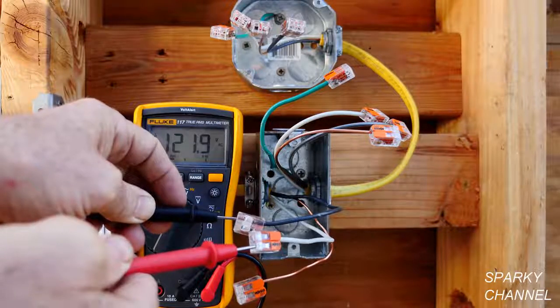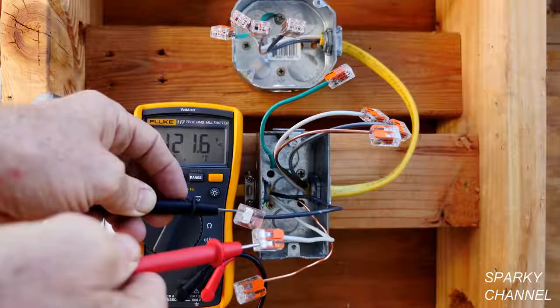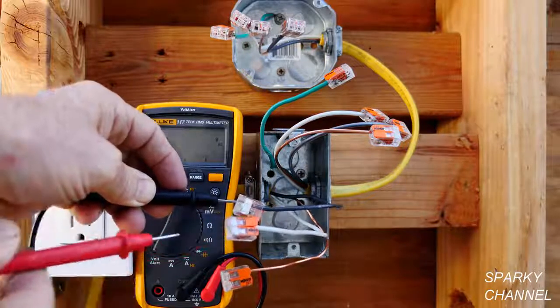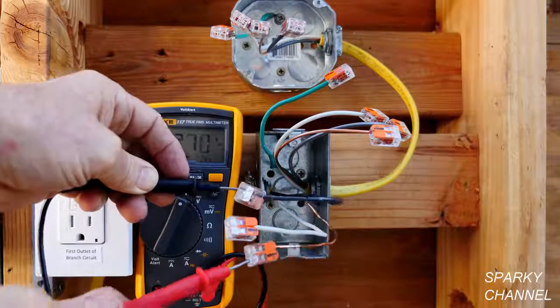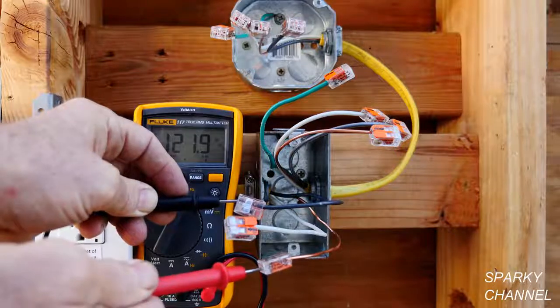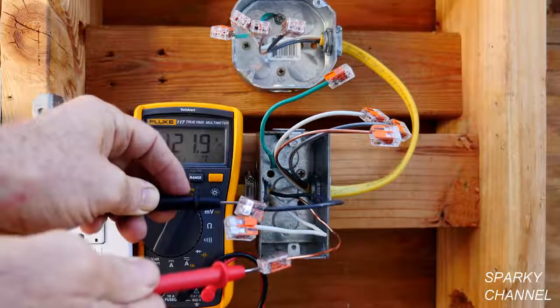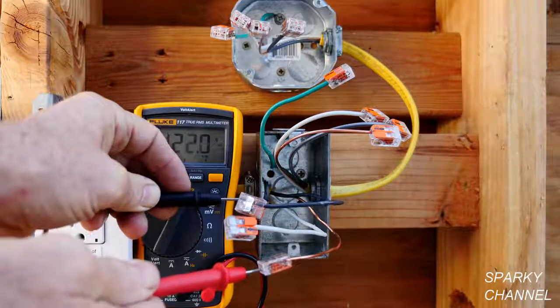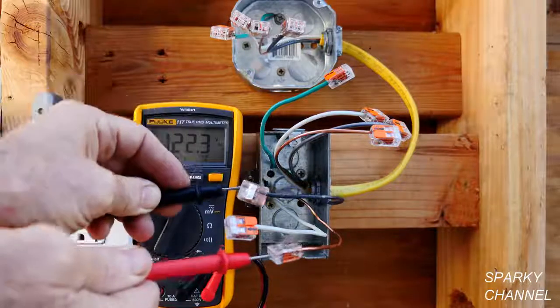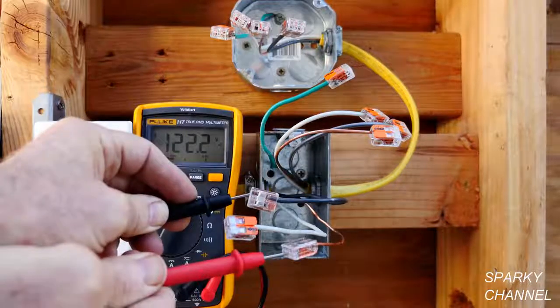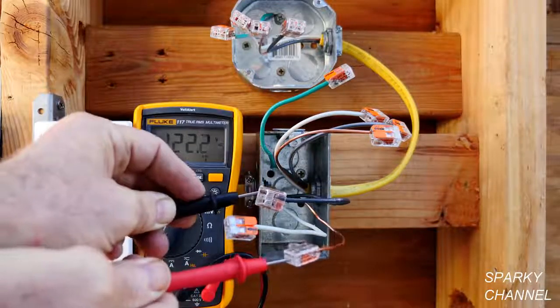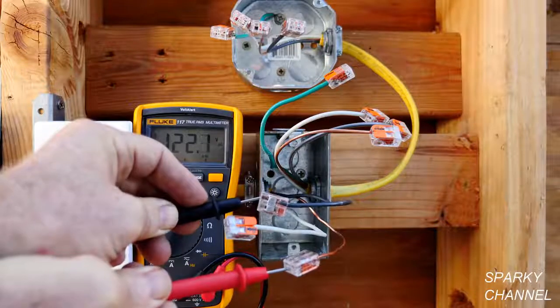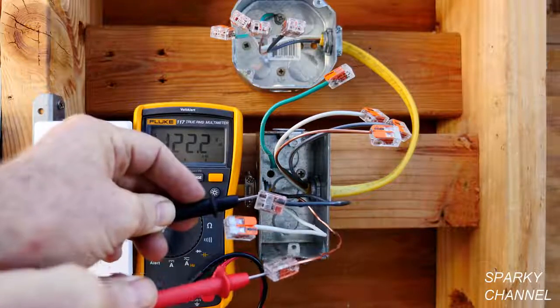So we have excellent voltage coming into the system. Now, we can also test the ground. I'll take the lead out of the neutral and I'll put it in the ground wire. And we have 121.9 volts AC. So that shows us that we also have an excellent ground. We have excellent voltage coming into the box, and we have an excellent ground.